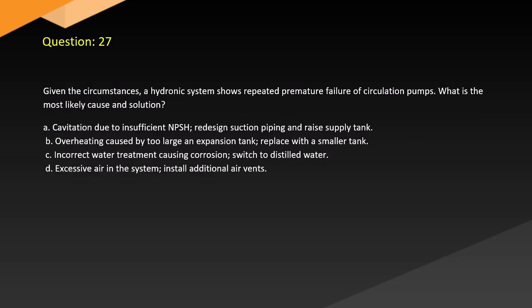Question 27. Given the circumstances, a hydronic system shows repeated premature failure of circulation pumps. What is the most likely cause and solution? A. Cavitation due to insufficient suction head, need to redesign suction piping and raise supply tank. B. Overheating caused by too large an expansion tank, replace with a smaller tank. C. Incorrect water treatment causing corrosion, switch to distilled water. D. Excessive air in the system, install additional air vents.